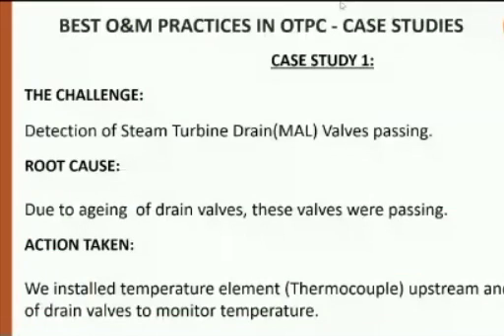Now I will share a few of the case studies. These were challenges related to uninterrupted power generation from the plant, or to reduced downtime of the plant. I will share case study number 1. This was related to the steam turbine drain valves passing. Due to drain valve passing, the vacuum was not good in the condenser, and we were having a poor heat rate. Apart from that, we had a problem of top-bottom casing temperature difference near the alarm value. This is a common problem in most power plants. Basically, this occurs due to erosion of the drain valve, which results in the passing of the drain valve.